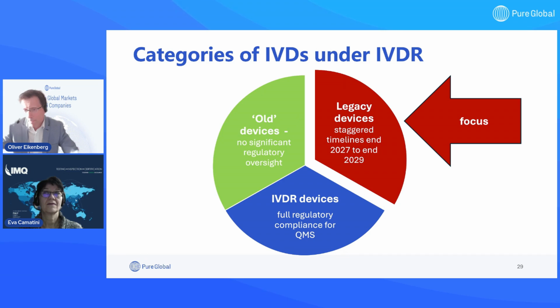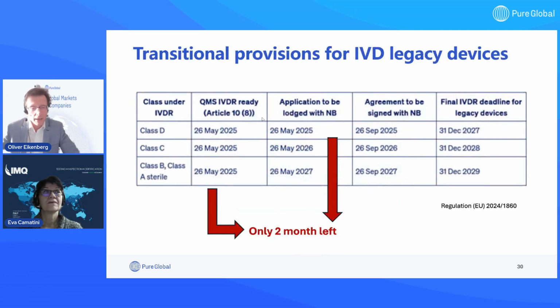And I believe many of these on the market are still legacy devices. And many still believe that these staggered timelines are the final timelines. It's not the starting point, it's the end timelines, and maybe you have not started to act because you believe you have a long time. So I will focus a little bit on these because we have some transitional provisions for these legacy devices introduced by the European Commission. And one is applying in May 2025. And this is only 2 months left to have a QMS already IVDR ready, according to Article 10(8).